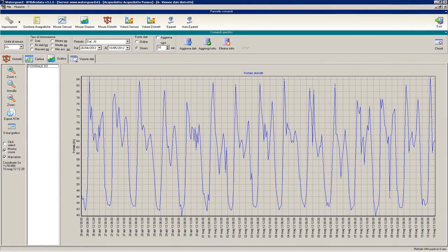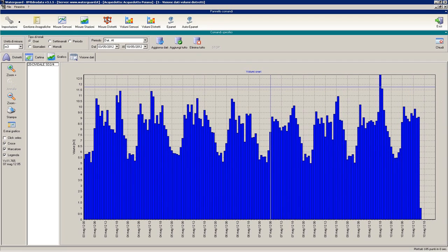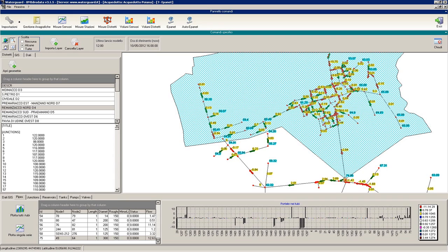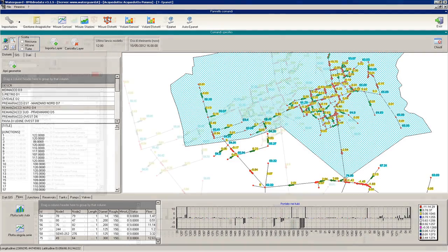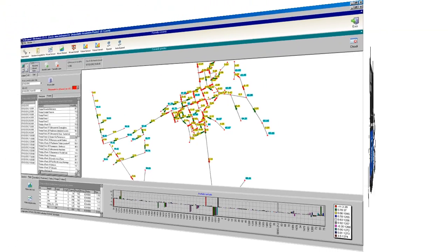The data collected at each measuring station may be displayed in plots showing flow, pressure, flow and pressure together, volume per hour, day, week, month, and as a function of any time interval set by the operator. The EPANET code for calculation of water network pressure is integrated in WaterGuard. This numerical engine allows simulation of the working status of the whole system in real time. Only the geometrical features of the water supply network need to be specified by the user. The numerical code identifies the trend of pressure, flow rate values, and flow direction, and allows continuous simulation of network behavior using data collected by the instruments and validated by WaterGuard. Hindcasting can also be performed by uploading previously recorded data and simulating network behavior for that period or situation.